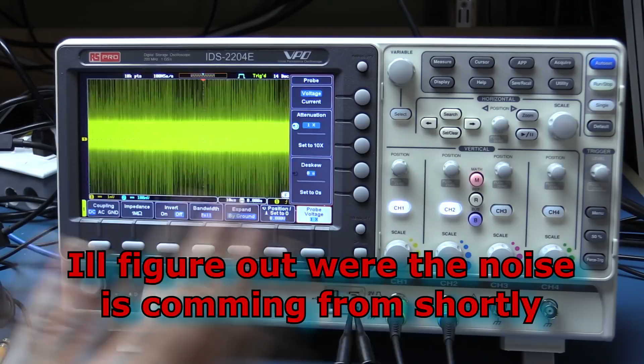It's fairly typical on this level of resolution. So you've got 10 millivolts per division. We change that to ×1. Now you've got your 1 millivolt. But these probes are 10 times probes. You cannot switch them to ×1, right? They're fixed at ×10. So it means that with the standard probes that come with this, you can't do your 1 millivolt per division.